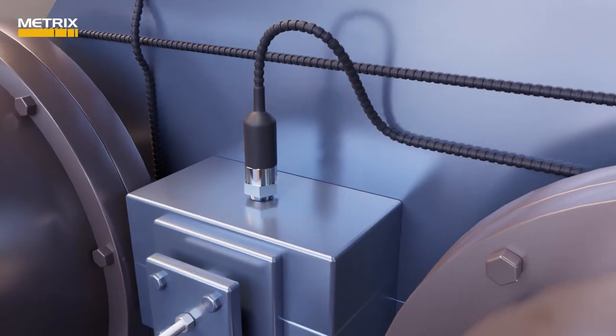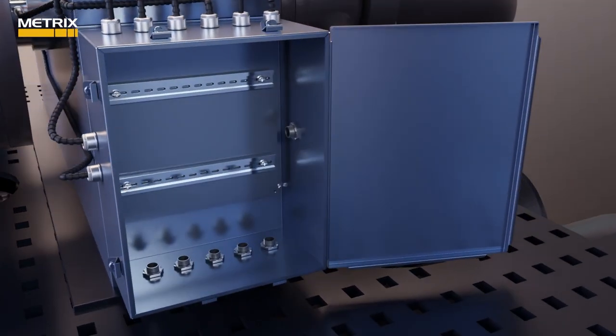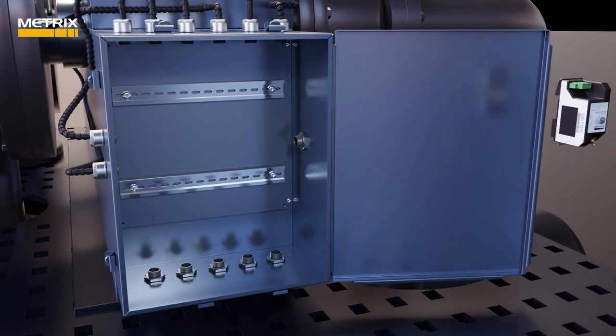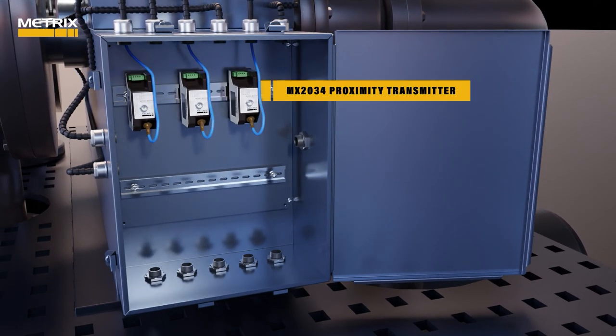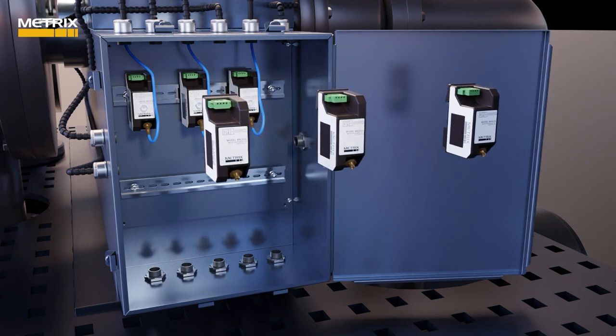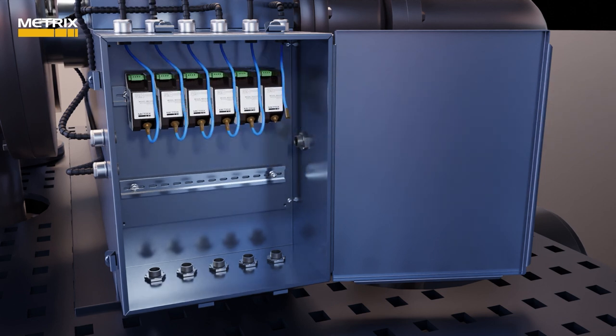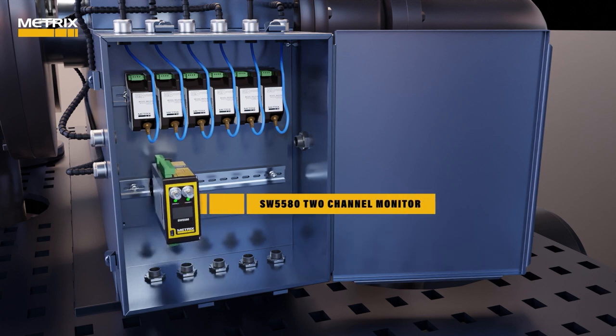Depending upon the criticality of the machine, packaged air compressors are usually monitored with a single proximity probe near each impeller using an MX2034 proximity transmitter, with its output going to the control system. In the process compressor case, each impeller is monitored with two proximity sensors in an XY fashion using two MX2033 drivers to a vibration monitoring system like the SW5580 two channel monitor or other VMS.